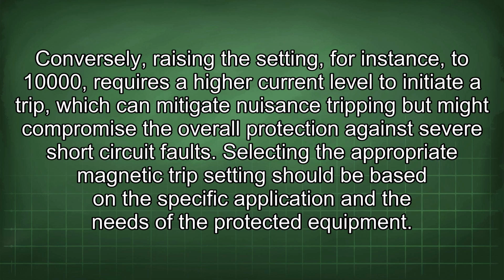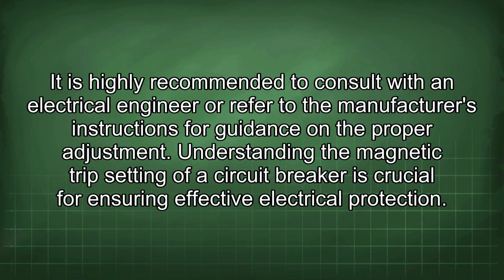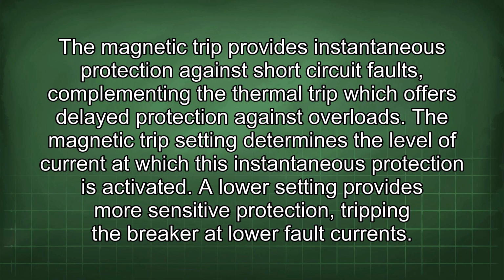Selecting the appropriate magnetic trip setting should be based on the specific application and the needs of the protected equipment. It is highly recommended to consult with an electrical engineer or refer to the manufacturer's instructions for guidance on the proper adjustment. Understanding the magnetic trip setting of a circuit breaker is crucial for ensuring effective electrical protection. The magnetic trip provides instantaneous protection against short-circuit faults, complementing the thermal trip, which offers delayed protection against overloads. The magnetic trip setting determines the level of current at which this instantaneous protection is activated.